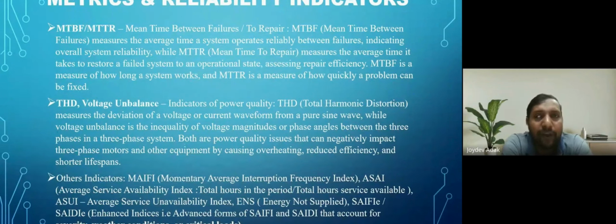In ideal condition, the supply should only contain the fundamental frequency. But that ideal condition is not present in any system. So THD is calculated. Other indicators are MAIFI, momentary average interruption frequency index, ASAI, average service availability index, ASUI, average service unavailability index, ENS, energy not supplied, and modern SAIFI and SAIDI, enhanced indices, that is an advanced form that also considers severity, weather condition, and critical loads.